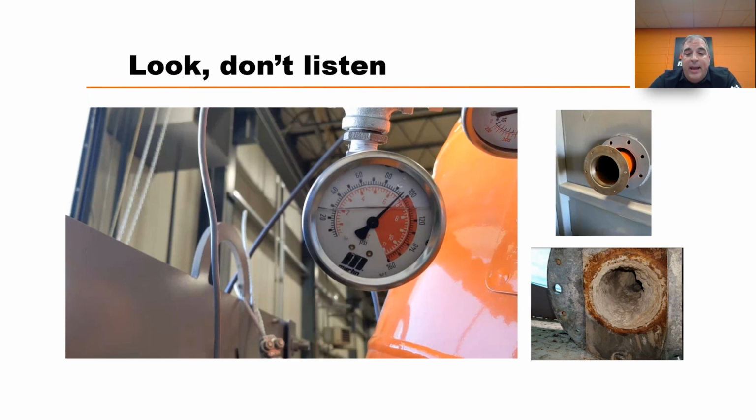Cannons are loud, and there's usually a couple of different valves that have to operate to make the cannon work. If you're just listening to it, you're going to hear a pop, and the person who pushed the solenoid or actuated the cannon hears a pop, and they think, oh, that cannon worked. Well, that isn't necessarily the case.